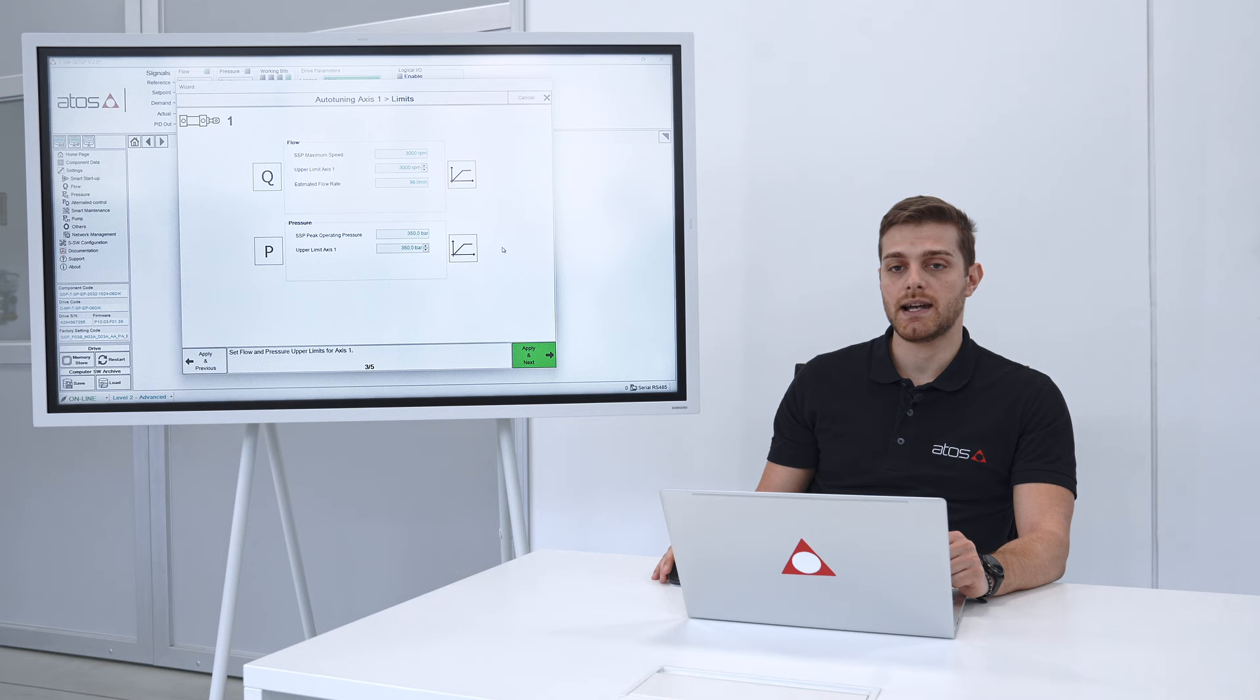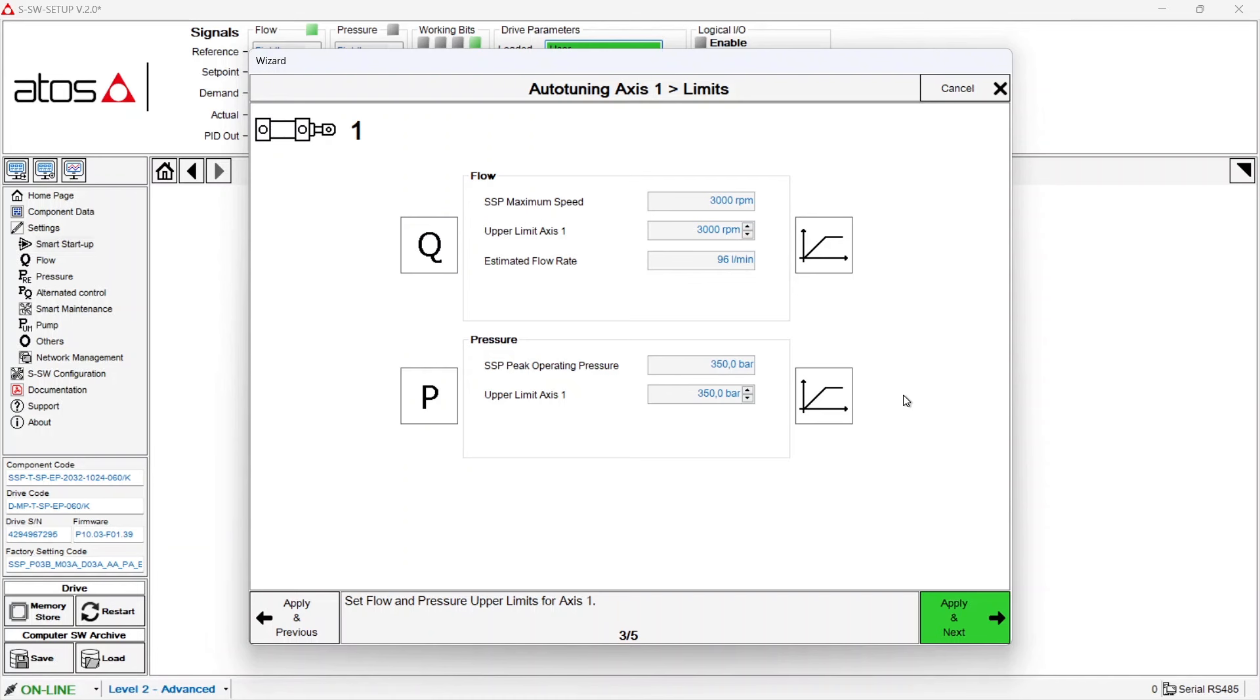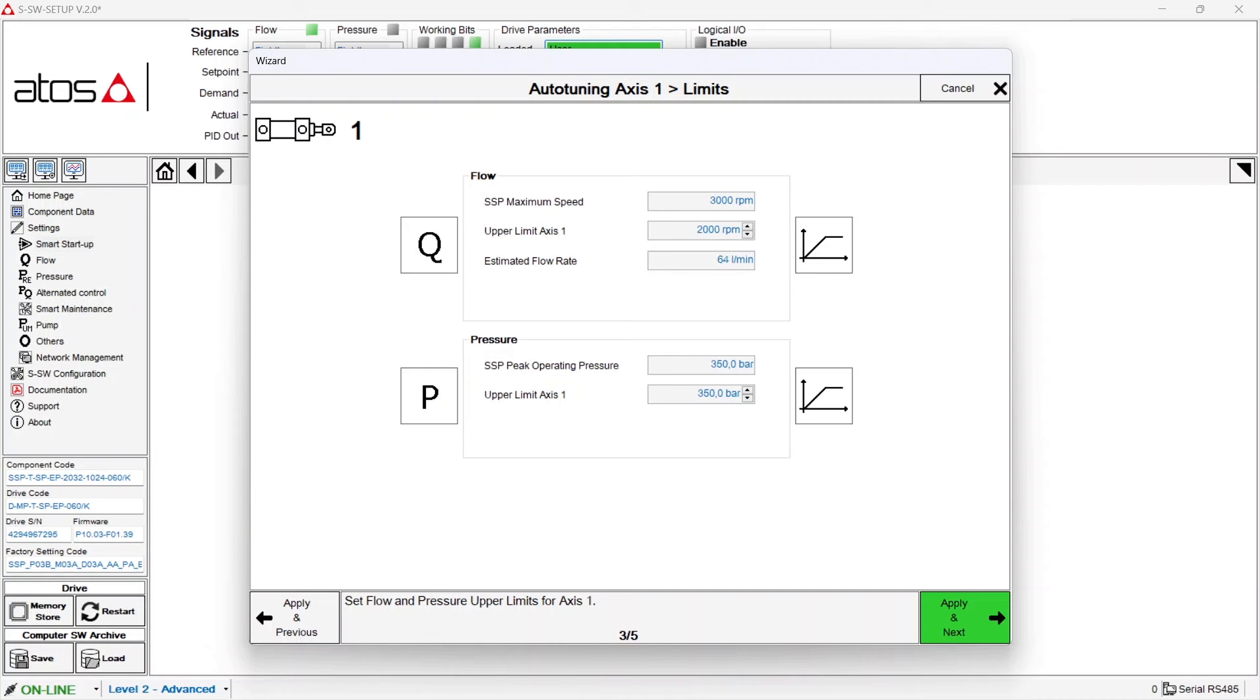This step instead allows to set the limits of your cylinder. This servo pump we are using allows to have as maximum flow rate 96 liters per minute. If you don't want to have this high flow rate for this cylinder you can limit the maximum speed, for example to 2000 RPM. The same holds for the pressure. In this case for our test bench we have no limitation. After you set the parameters again apply next.